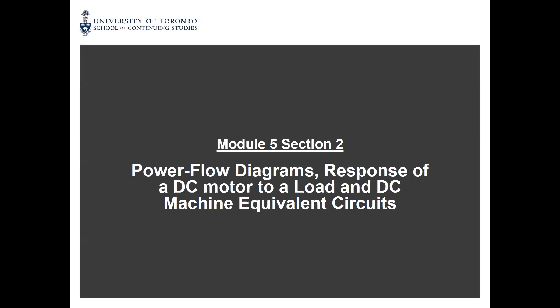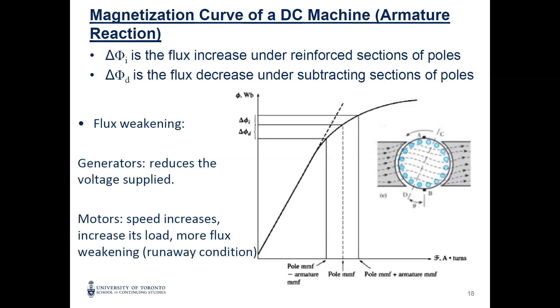After that, we discussed the power flow. First is the armature reaction, which in general weakens or reduces the flux in the machine. For generators, the impact is reducing the voltage. For motors, it's more dangerous because it increases the speed until you reach a runaway condition, potentially breaking your shaft.